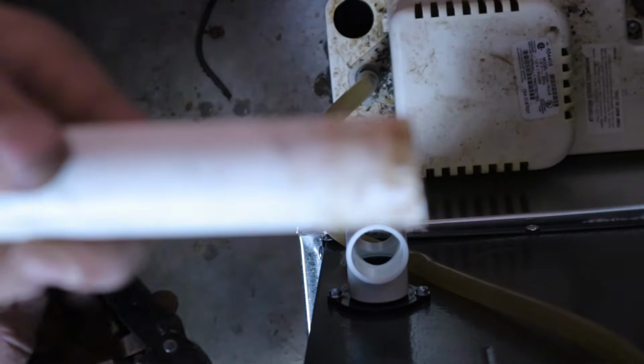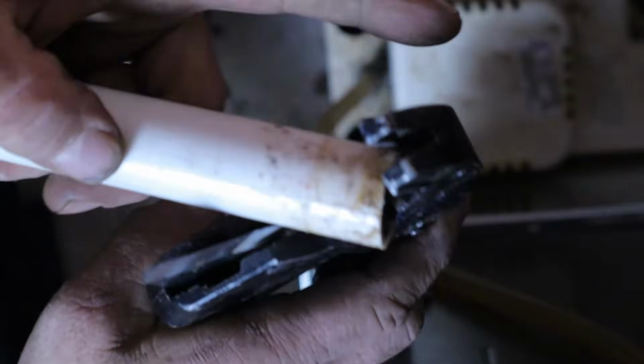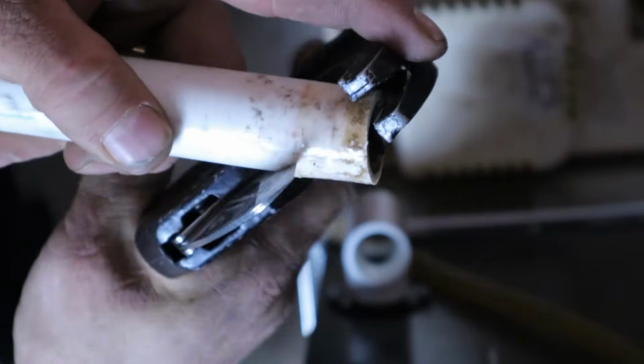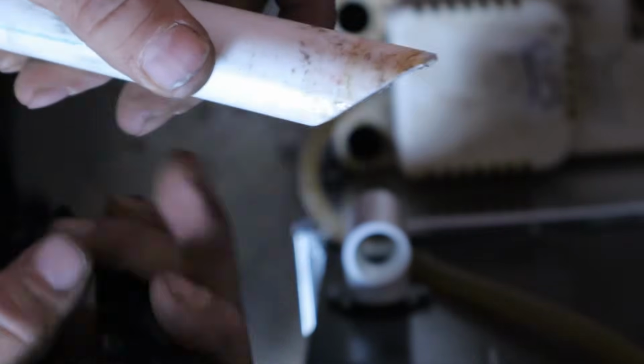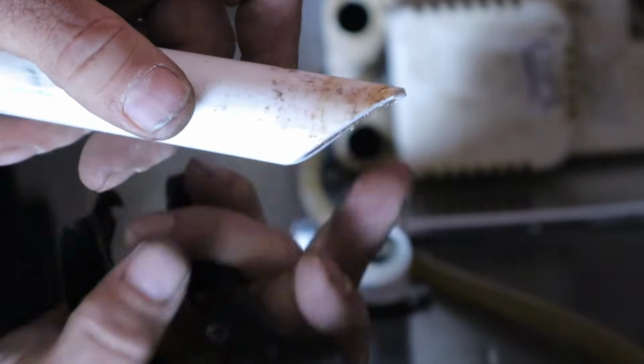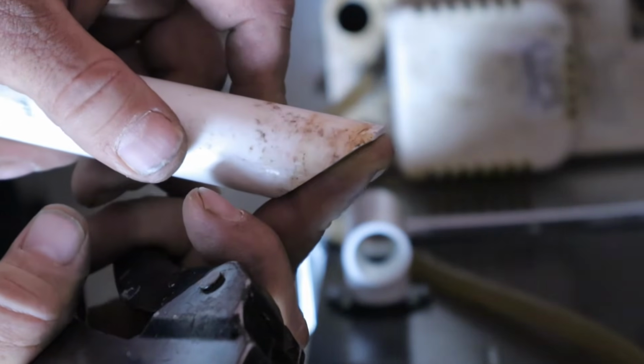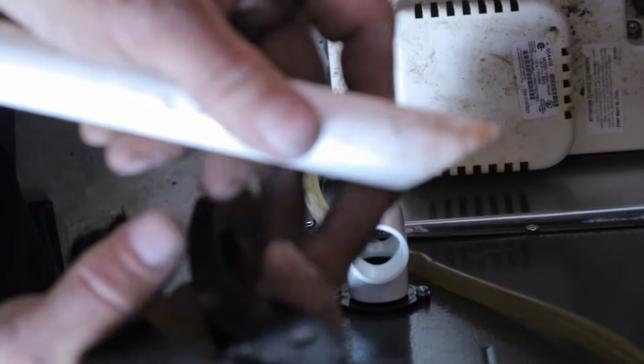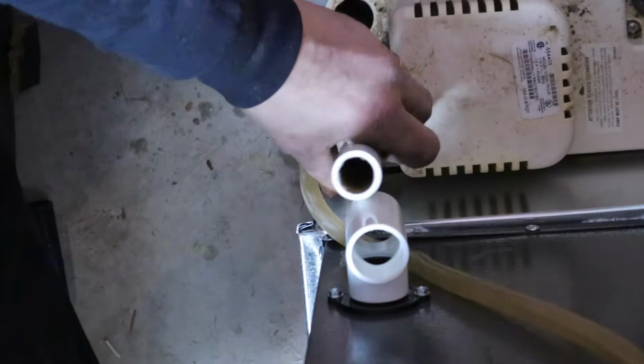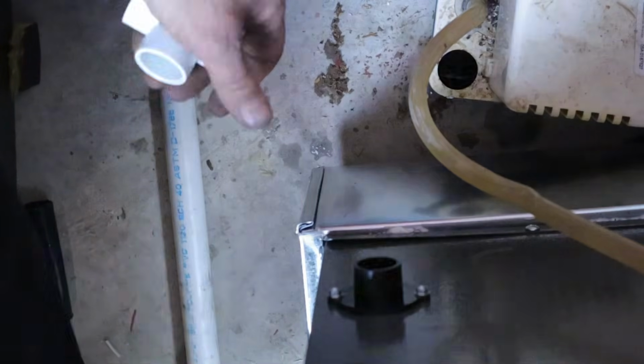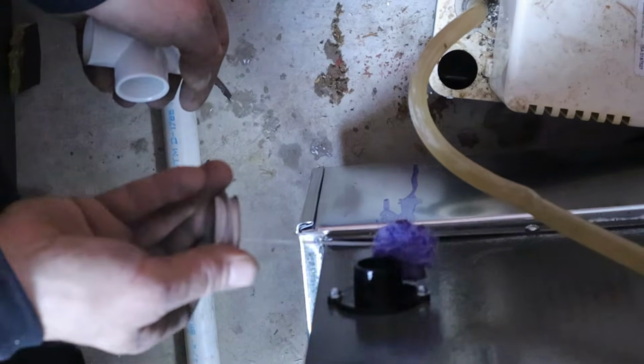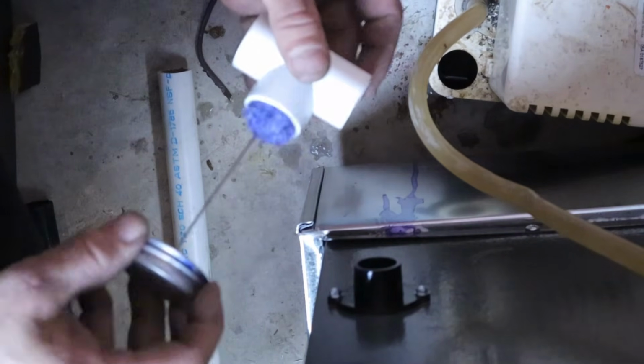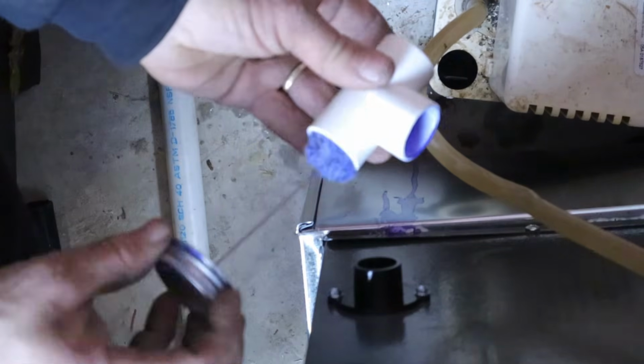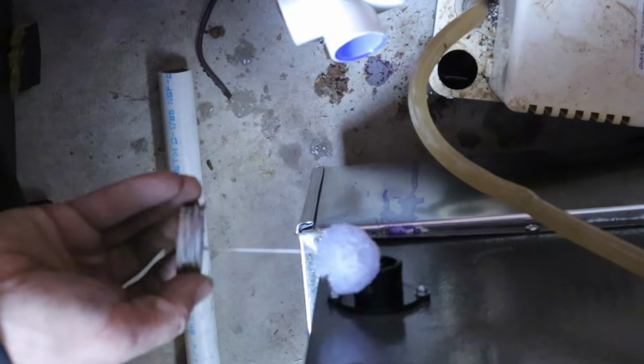Now what I like to do with this PVC is, you can see there's a flat edge on the PVC where it's cut. I like to cut an angle into it, so when it sits in the condensate pump, there's no chance of it sitting flat on the bottom of the pump and blocking the opening up, and the water will back up into the furnace and it'll shut it down. So I put that on there so that can't happen. So that side goes down into the condensate pump. Put some primer on that black fitting. Primer inside my T. And I'm going to just go ahead and glue it in.